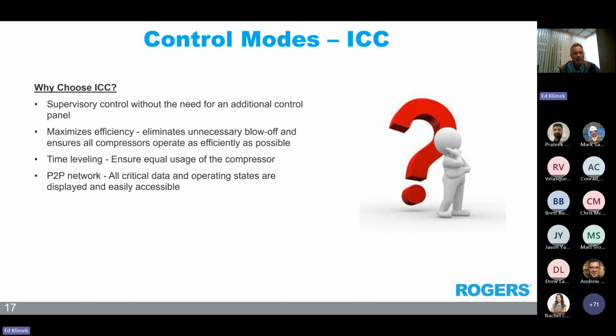Why would the ICC be important? You have less operator interaction, maximum efficiency that maximizes the turndown and eliminates unnecessary blow-off. Rotation of standby compressors to ensure equal usage, especially if you're utilizing the time leveling feature. It minimizes the wear and tear of your compressors.